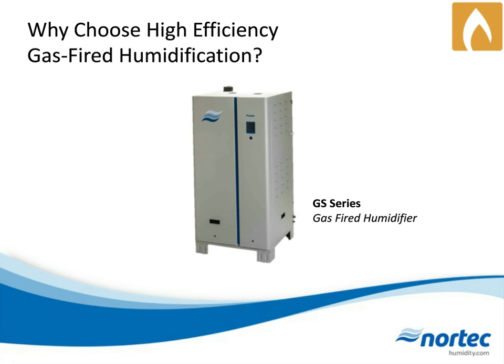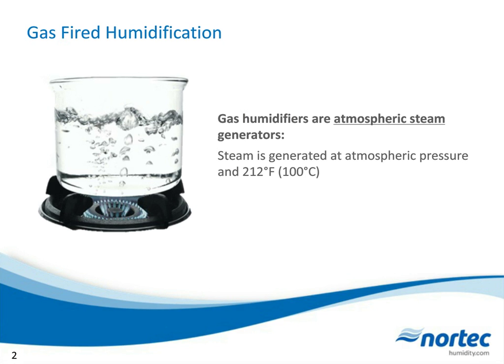Why are we choosing high-efficiency gas-fired humidification? First, let's talk about what it is. It is an atmospheric steam generator — at its core, we are boiling water with gas at atmospheric pressure. There is not a lot of head generated here. We can't overcome large pressure differentials, so when we talk gas-fired humidification, we are talking isothermal atmospheric steam generation.